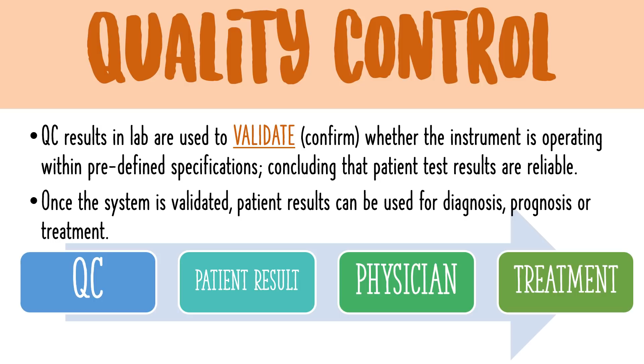So how do we perform basic quality control measures? We are going to retrieve a control sample, and this control sample is going to be run in the machine or run with the procedure that we use in the laboratory. It could be run separately or it could be run along with the patient samples randomly. Once running is done, we get the result of our quality control sample, and it is expected that these results must be within the range of values provided by the manufacturer in the product insert.